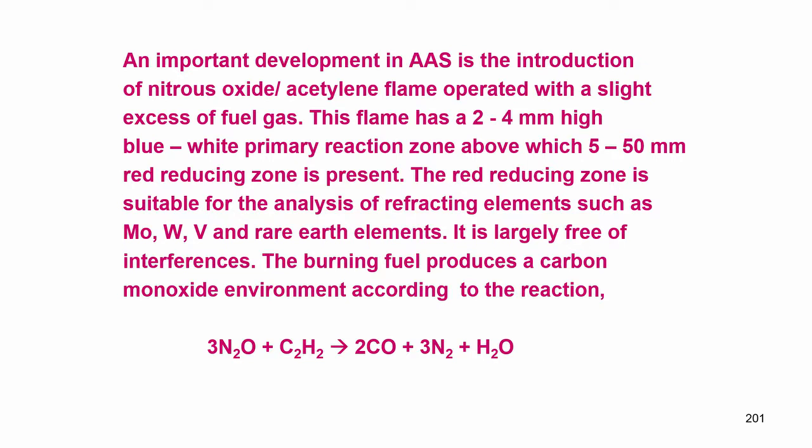So, the burning fuel produces a carbon monoxide environment according to this reaction: nitrous oxide will react with acetylene to produce carbon monoxide, which is a reducing agent, and the other products are nitrogen and water. So, all these things will be in the gaseous state whenever you are operating a nitrous oxide acetylene flame.